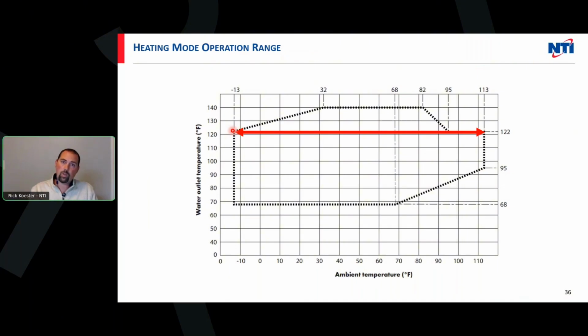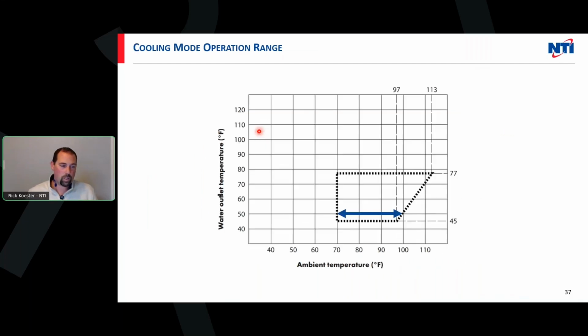So my BTUs may diminish on my output side, going to those heat emitters. So I've got to be careful when I'm designing a system that if I do need that water temp, I can see from this chart that I may need to bump up the equipment or do multiple different things, right? But I have an idea of what consistent water temperatures this machine will be able to give you.